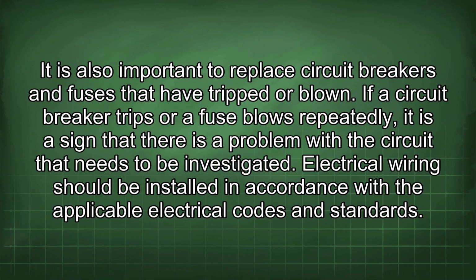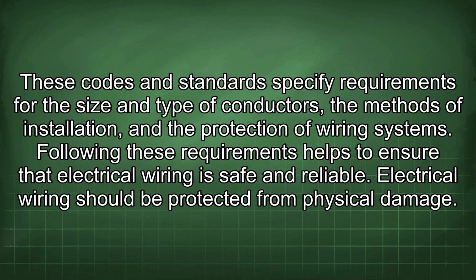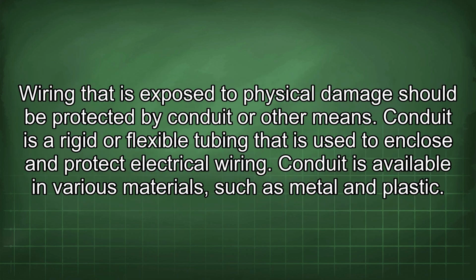Electrical wiring should be installed in accordance with the applicable electrical codes and standards. These codes and standards specify requirements for the size and type of conductors, the methods of installation, and the protection of wiring systems. Following these requirements helps to ensure that electrical wiring is safe and reliable. Electrical wiring should be protected from physical damage. Wiring that is exposed to physical damage should be protected by conduit or other means.